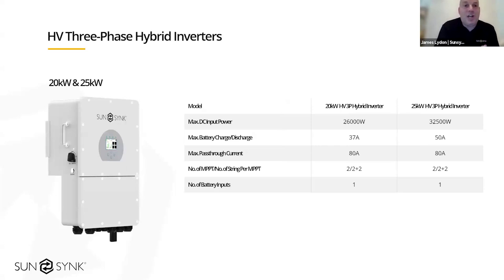Okay, so now our high voltage hybrid inverters. When we say high voltage, they're still standard three-phase. The high voltage is on the battery side, which we'll come to in a minute. On our high voltage, we do a 20 and a 25 starting off with. On the 20 kilowatt high voltage three-phase, we've got a 26 kilowatt MPPT. That's over 4 strings. And then the 25 kilowatt high voltage three-phase, that's got a 32.5 kilowatt MPPT. Again, 2 MPPTs with 2 strings into each.